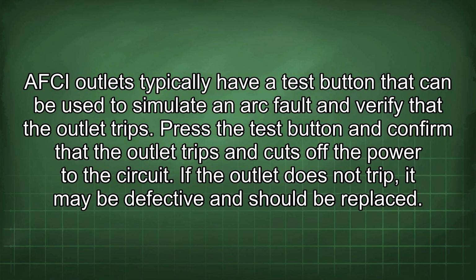AFCI outlets typically have a test button that can be used to simulate an arc fault and verify that the outlet trips. Press the test button and confirm that the outlet trips and cuts off the power to the circuit. If the outlet does not trip, it may be defective and should be replaced.